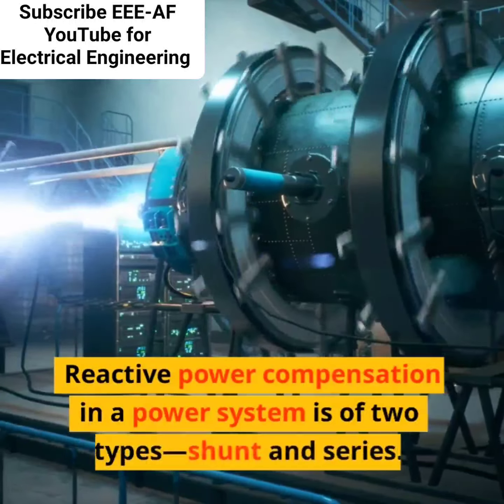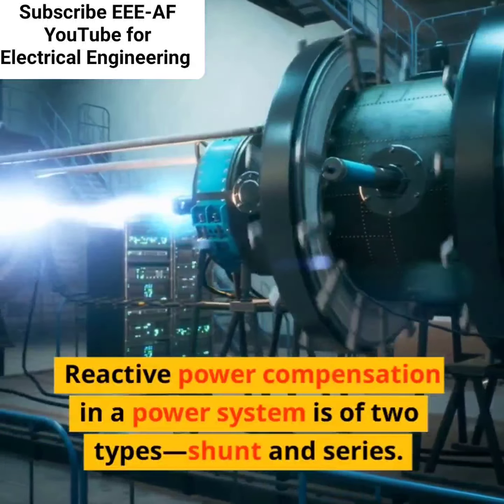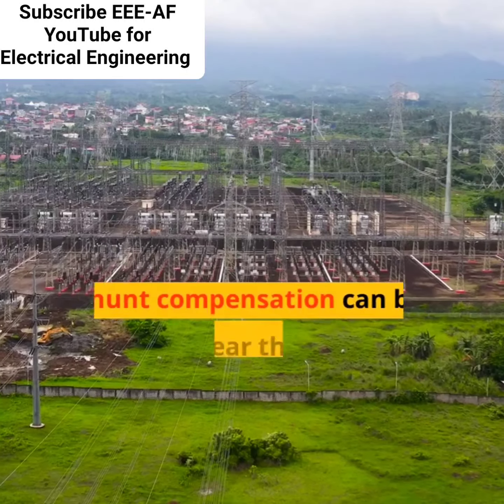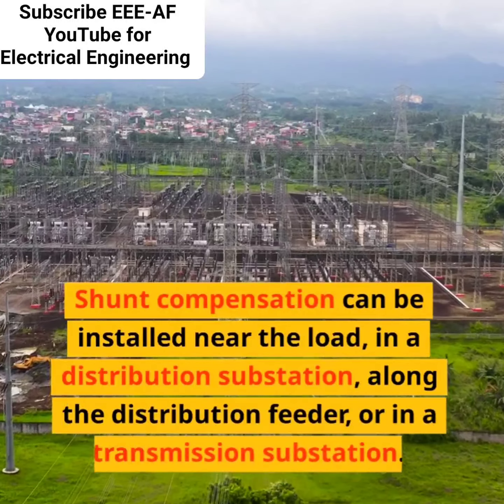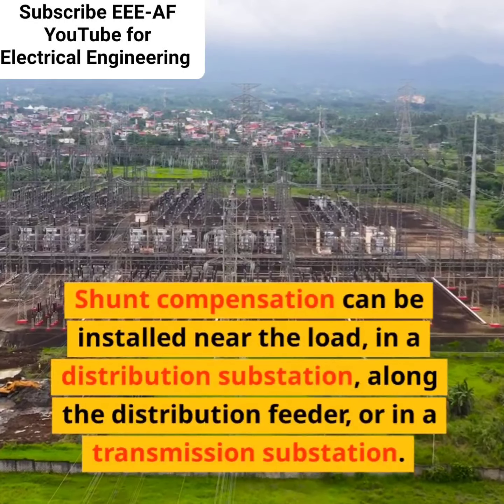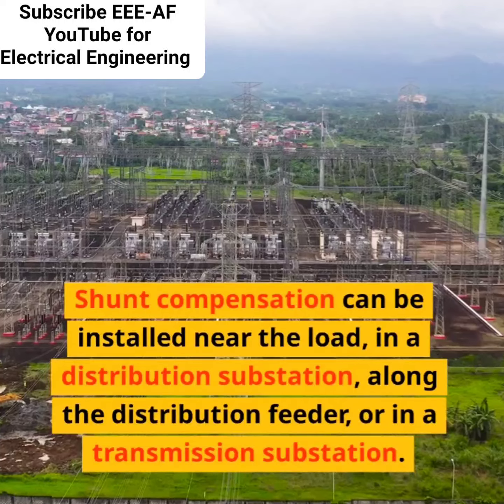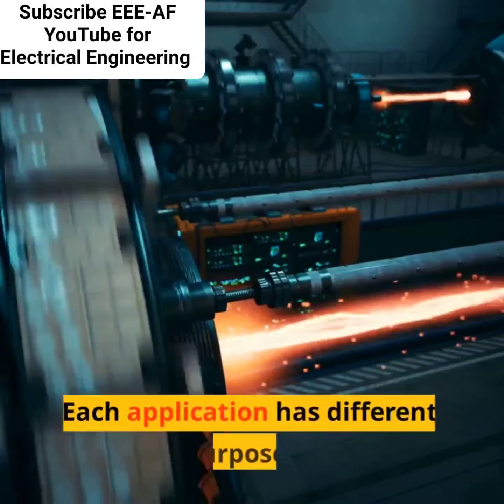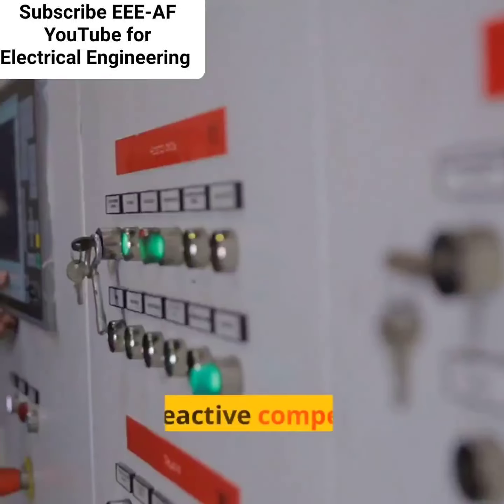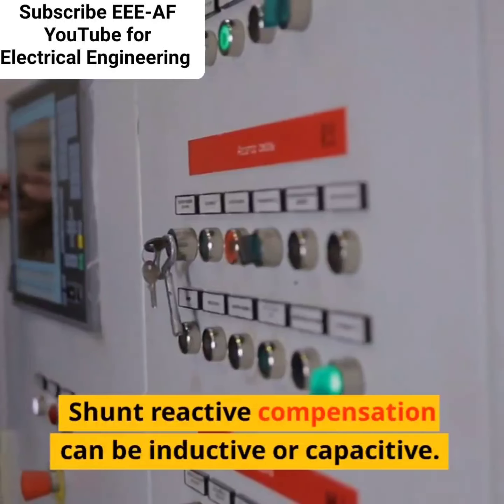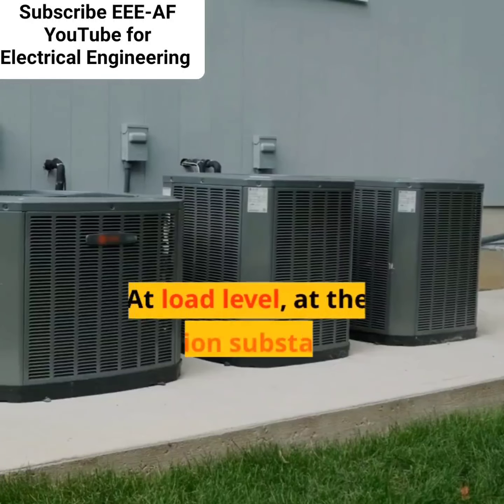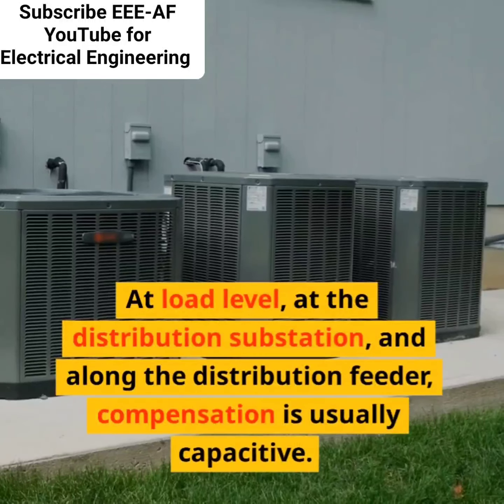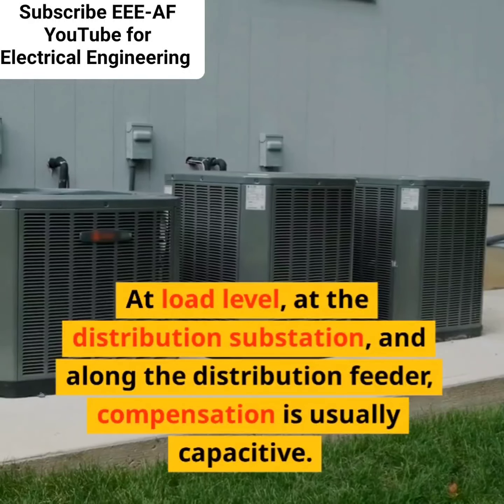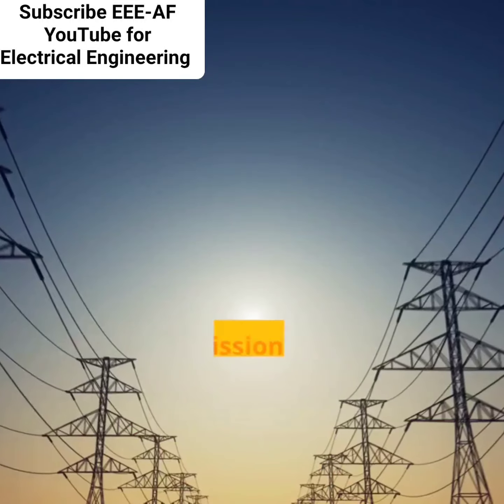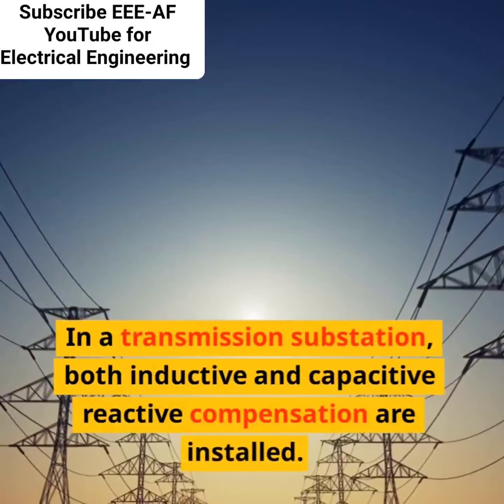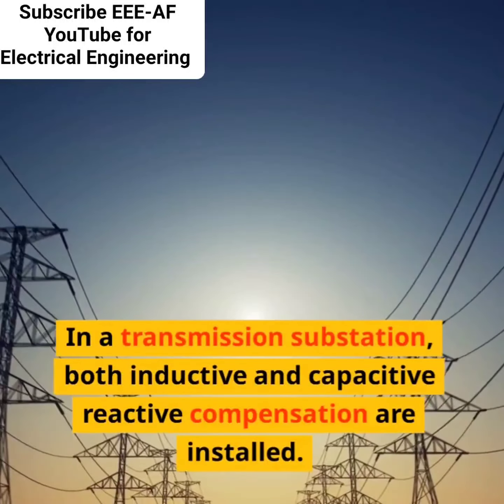Reactive power compensation in a power system is of two types: shunt and series. Shunt compensation can be installed near the load, in a distribution substation, along the distribution feeder, or in a transmission substation. Each application has different purposes. Shunt reactive compensation can be inductive or capacitive. At load level, at the distribution substation, and along the distribution feeder, compensation is usually capacitive. In a transmission substation, both inductive and capacitive reactive compensation are installed.